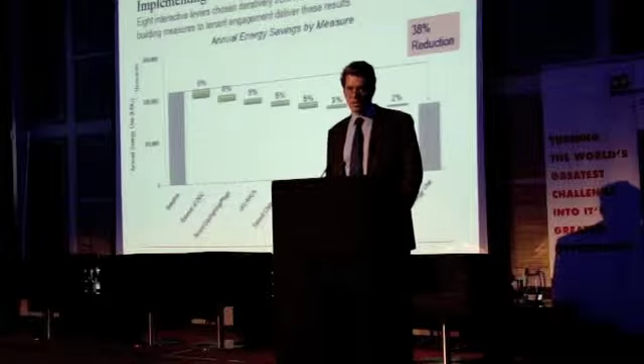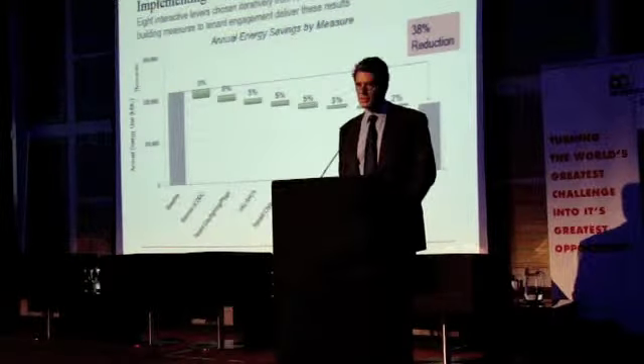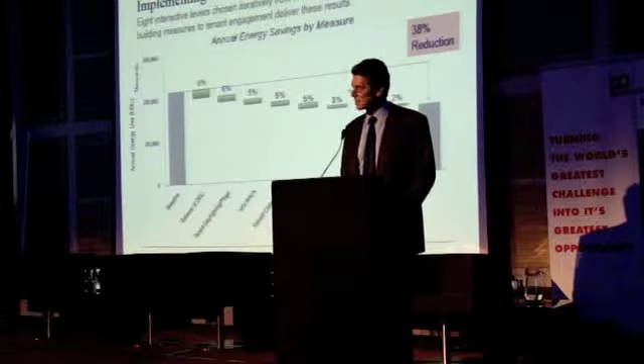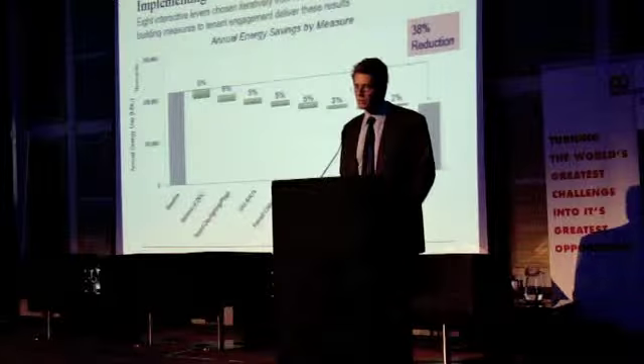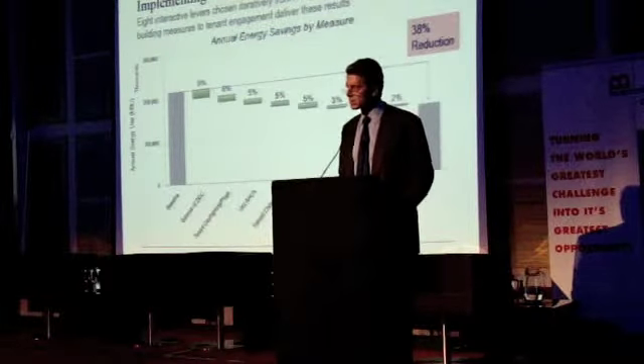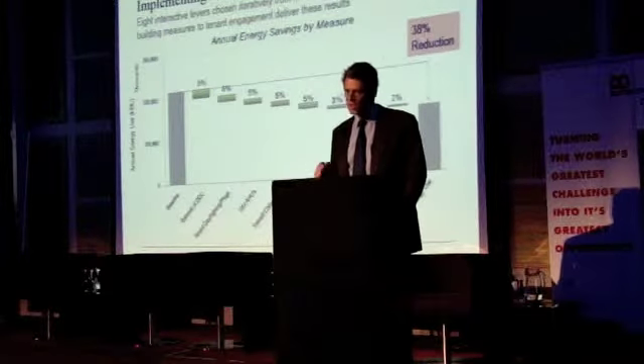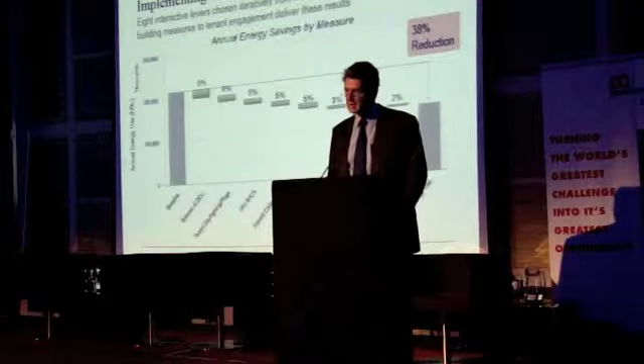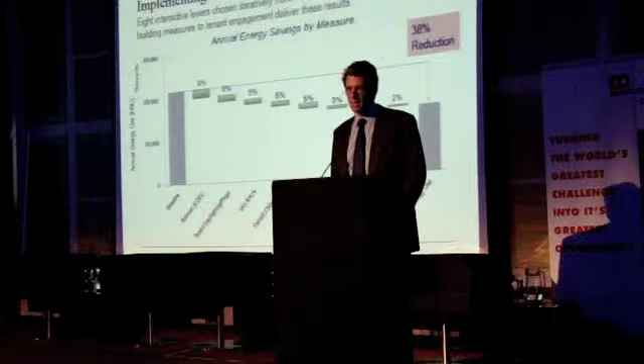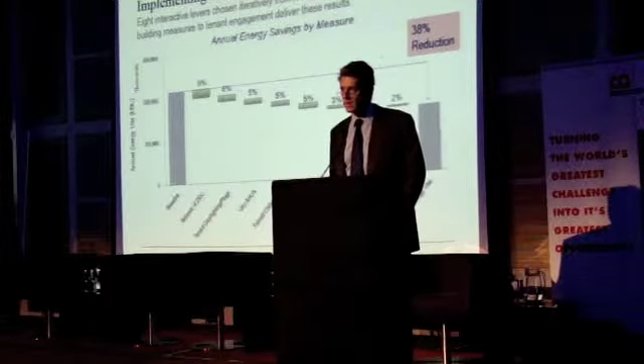I don't know if you guys are familiar with the R ratings, but air is 0 and a solid masonry wall with insulation is R15. Triple glazed, modern glass in a glass curtain wall building struggles to achieve R7, R8. We did this for about $700 a window versus $3,200 a window building new. We reused over 96% of the glass and window frames in our work. We got new windows which are warranted for more than 20 years.